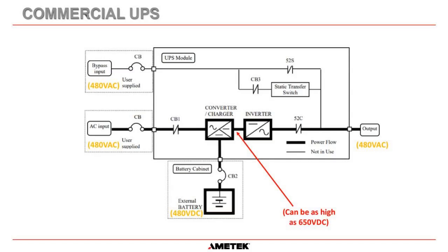The DC bus inside a commercial UPS can be as high as 650 volts DC, because there is just a bridge rectifier on the input that converts 480 volts AC into DC. Once again, this saves on cable sizing and IGBT sizes.